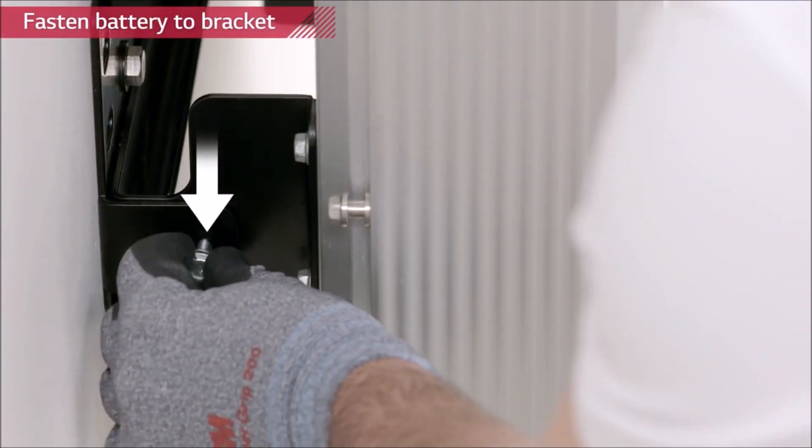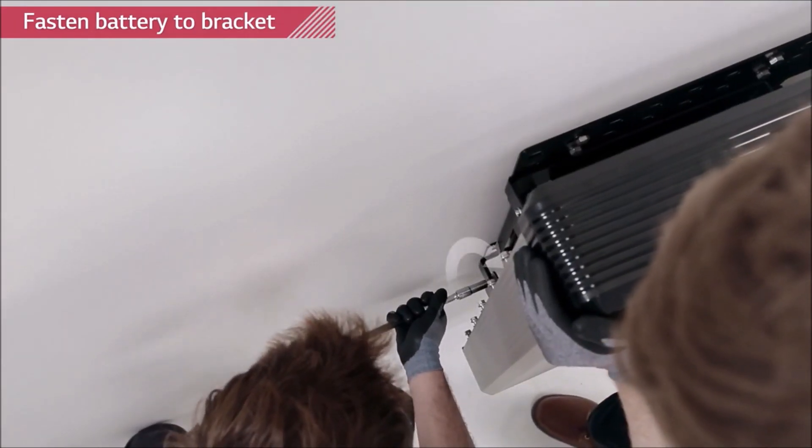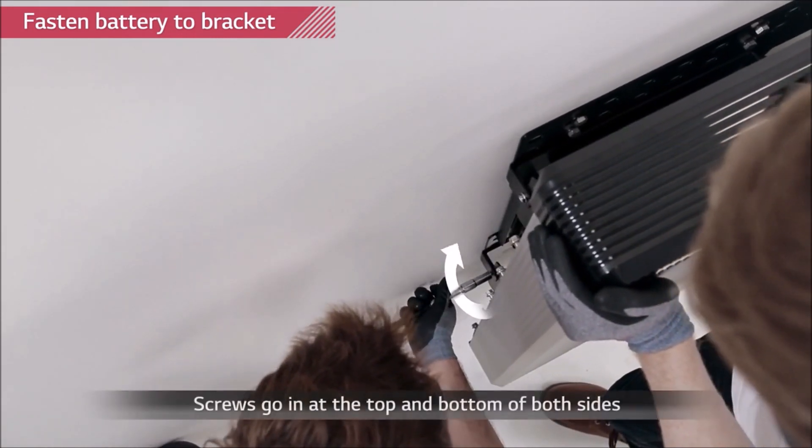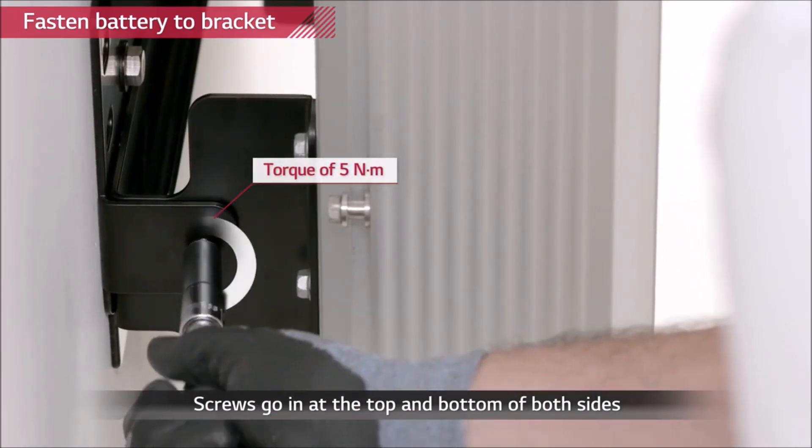Remove the lifting handles and tighten the two hex socket screws located at the back of left side of the battery pack with a torque of 5 Newton meters.